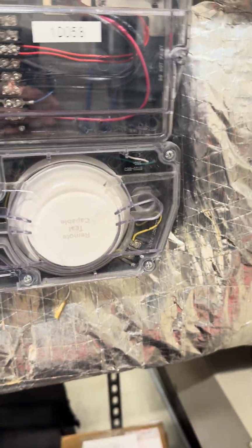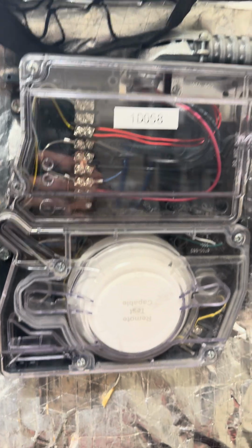So here's a good depiction of a duct detector. I'll come over here and get a little closer. These duct detectors are meant for detecting contaminated air within a system. I don't have a light, but that is the duct detector that can detect dirty smoke and then show it on the alarm panel that there is dirty smoke within the duct.